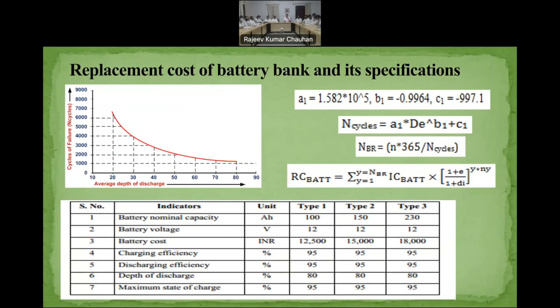So you have to think about what should be the minimum state of charge. If you go further below, the number of operating hours and number of cycles will be reduced, and you'll have to replace the battery continuously. That is very important, so accordingly you have to finalize this important operating point.